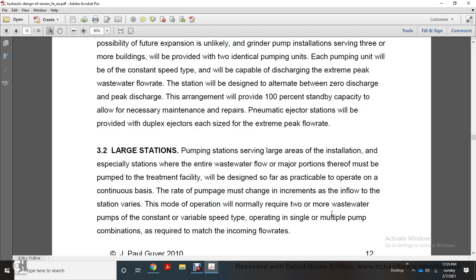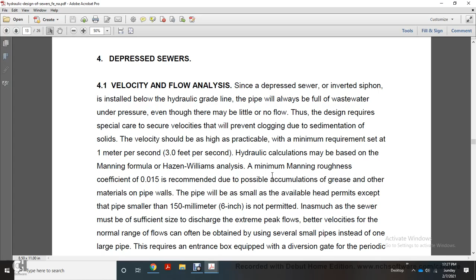4. Depressed sewers. Velocity and flow analysis. Since the depressed sewer is an inverted siphon installed below the hydraulic grade line, the pipe will always be under full water pressure, even though there may be little or no flow. Thus, design requires special care with velocity to prevent clogging due to sedimentation of solids. Therefore, the velocity should be as high as practical, with a minimum requirement set at 1 meter per second or 3 feet per second. Hydraulic calculations may be based on the Manning formula or the Hazen-Williams analysis. A minimum Manning roughness coefficient of 0.015 is recommended due to the possible accumulation of grease and other material on the pipe walls.